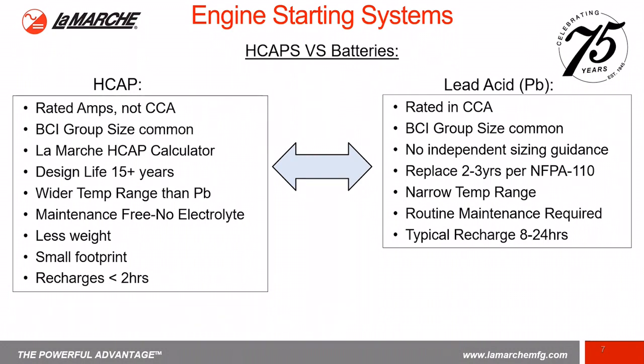There is no electrolyte. With the lead acid, there is sulfuric acid along with the electrolyte. HCAPs are a lot less weight. The footprint is small. And the other benefit, it can recharge in less than 2 hours, while with lead acid, typical recharge times are 8 to 24 hours, depending on the application. So as you can see, there are a lot of benefits going with LaMarche HCAP versus typical lead acid 8D or 4D type batteries for genset applications.